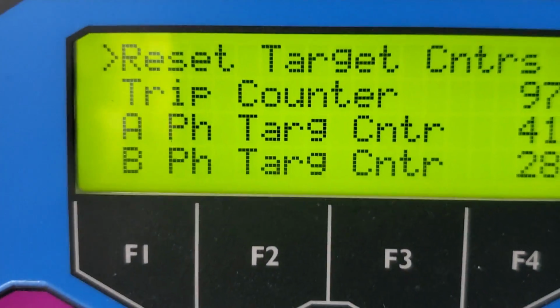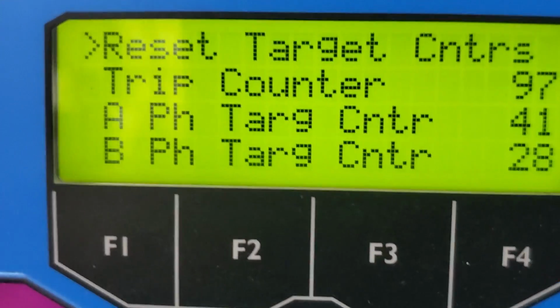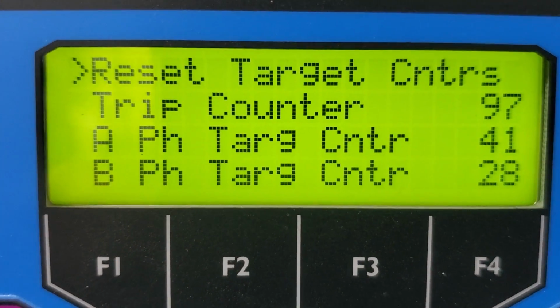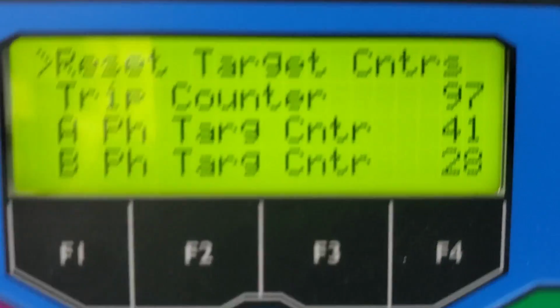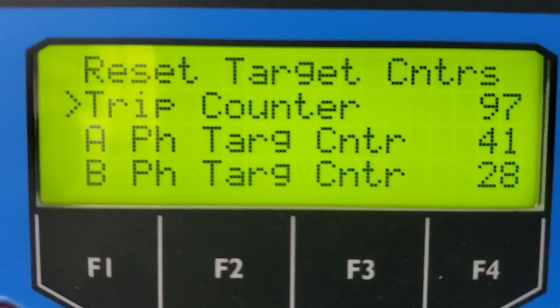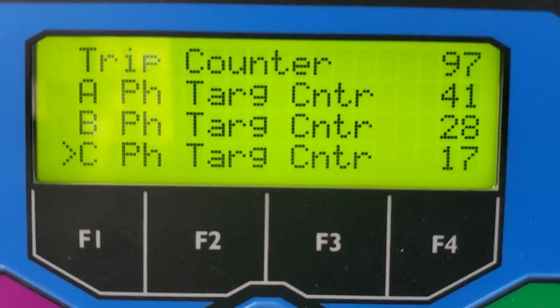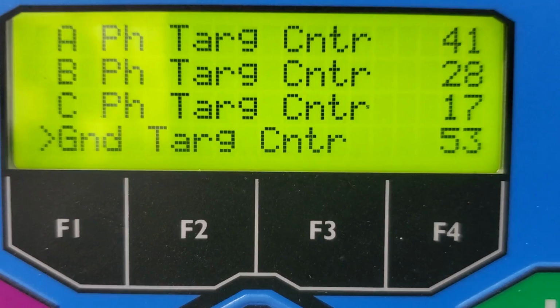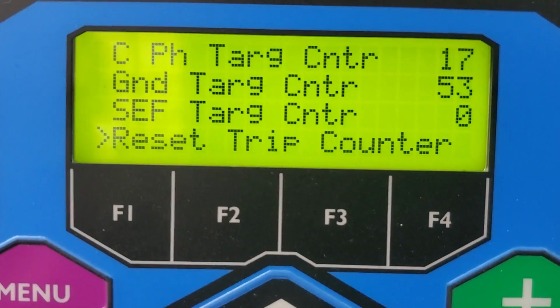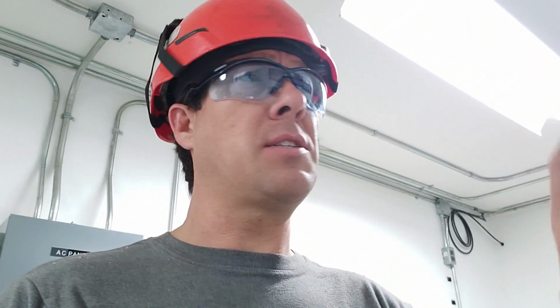So we are on one of our recloser panels here now. Having problems with the zoom here. There we go. So, trip counter. It's got 97 operations. Apparently my hands aren't very steady today. And it actually divides that up into each individual phase that caused the trip. Now, how that's useful is, you can also see it says reset trip counter. That's for this device only. The analog counter on the machine cannot be reset. Well, it can if it goes to the maintenance center.